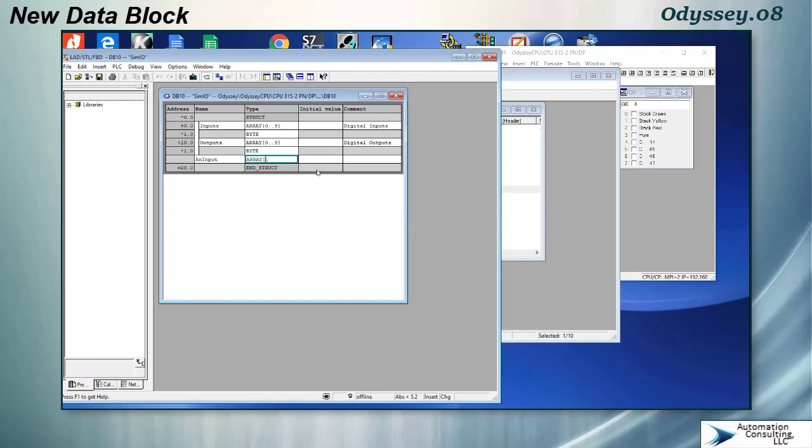And usually your analog process input words are in the higher registers, but I'm going to go ahead and number this, I suppose, just to show you that it's different. I'm going to make this one from 1 to 10. You do have to type this in exactly this way, 1 dot dot and whatever your endpoint is. This is kind of a nice feature for Siemens, that they'll allow you to start at 1 or 0.